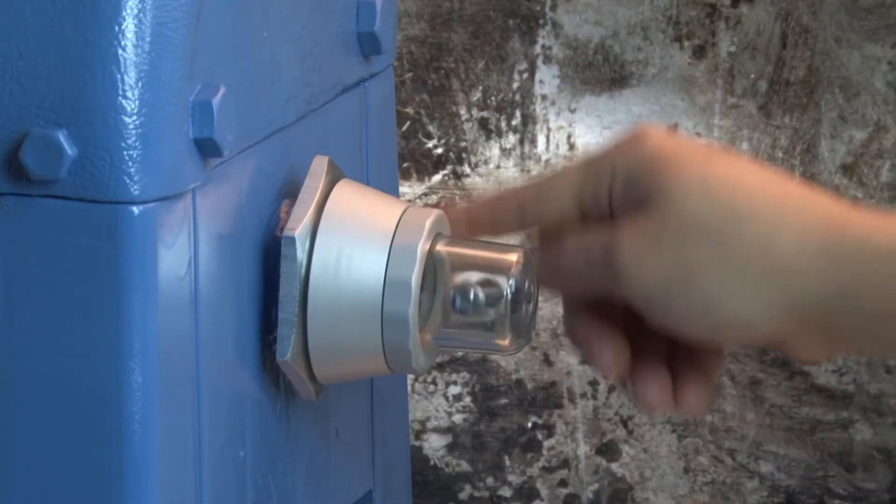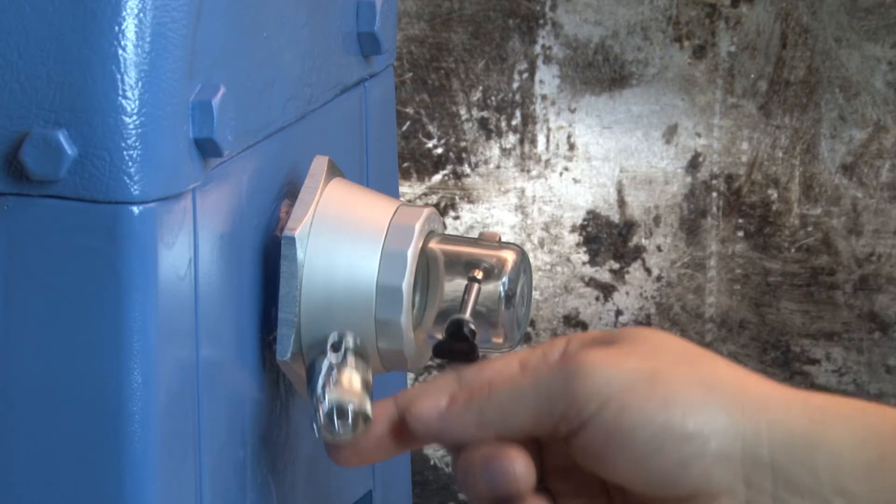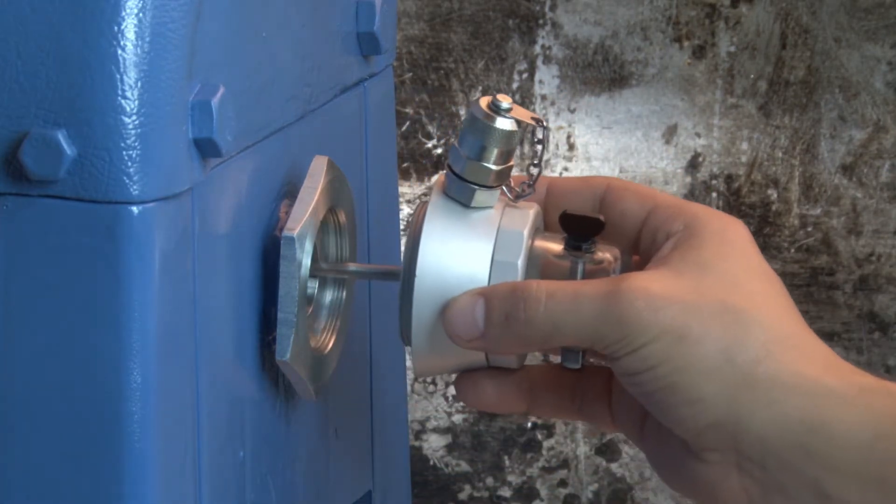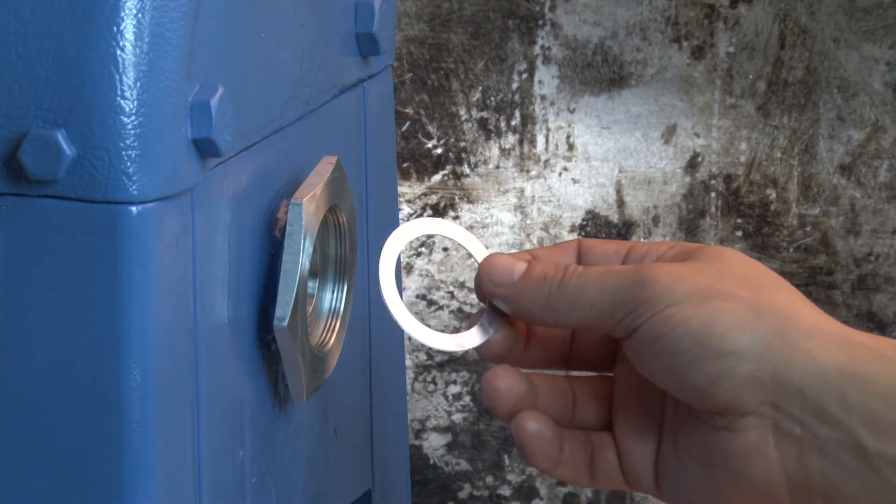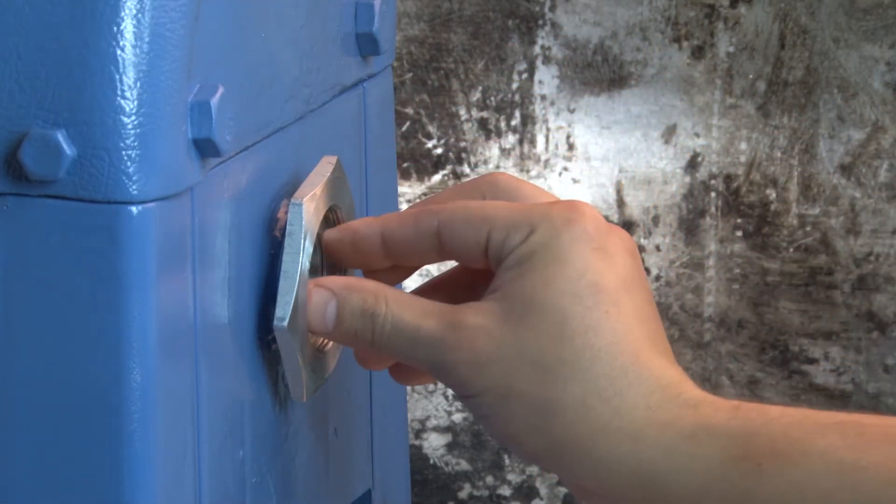Hand thread the CMP into the reducer. If the sampling port is not at a convenient location when fully tightened, use the supplied shims between the reducer and the CMP to reorient the sampling port. For this demonstration, the sampling port will be installed facing upward.